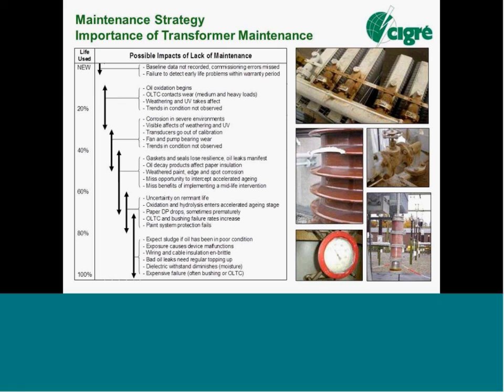But if you had a large generator transformer, supplying power to earn revenue from delivering power to the network, you're stuck in a dramatic way when the generator transformer fails, and it will take a long time to replace these large units, typically 7 to 12 months for a very large generator transformer to be specified, managed, delivered, erected, and commissioned. So clearly, no maintenance is not an option for these critical transformers. Any questions?